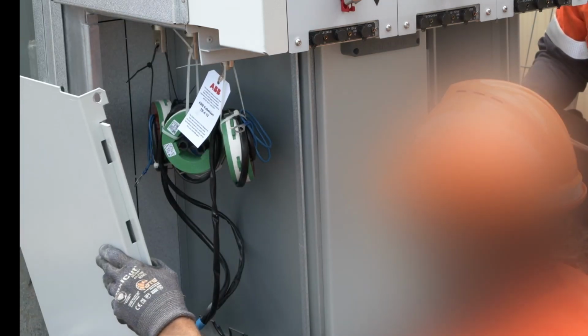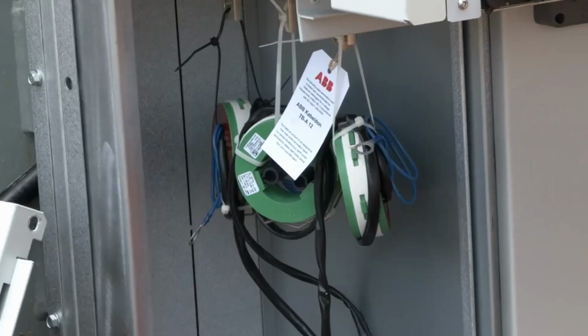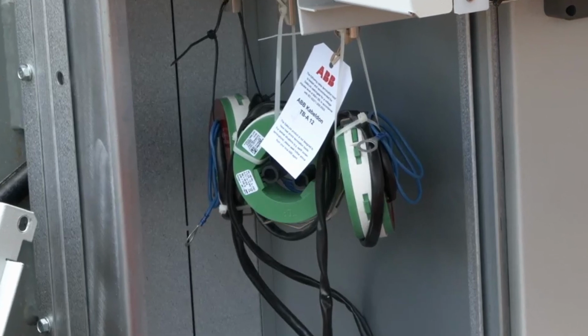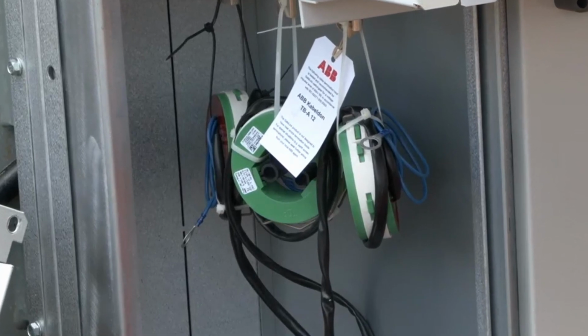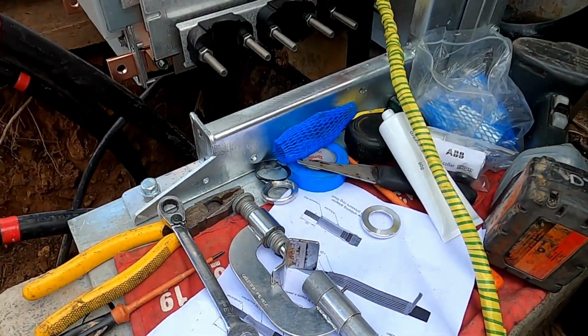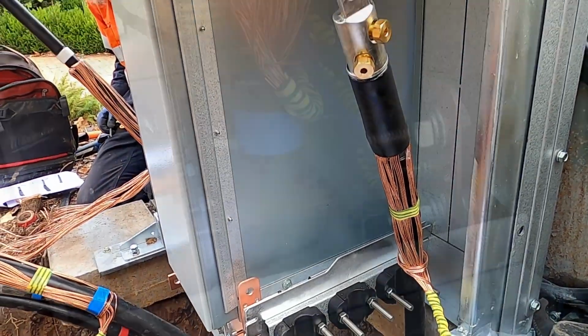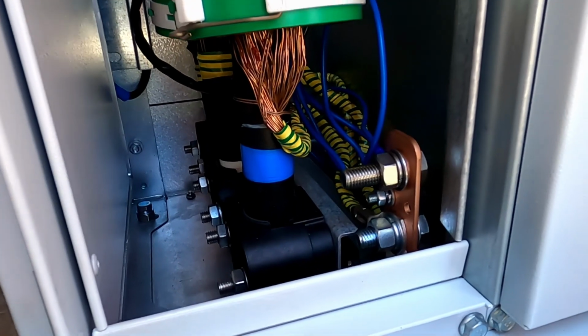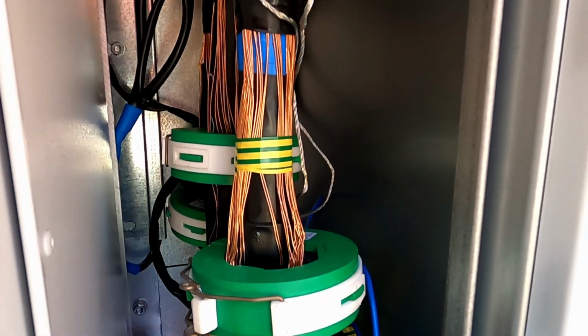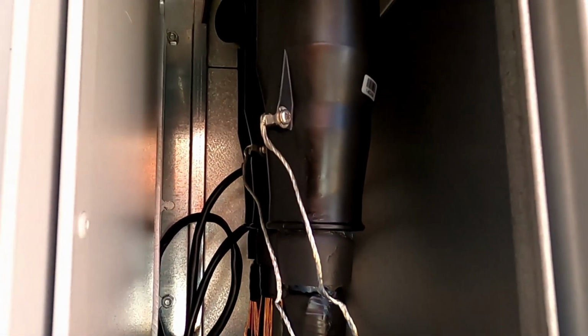Doors and side panels of the cable end boxes are removed to allow access for cable jointing. The CTs can be placed to the side until needed in the final stages of cable terminations. Perform all required cable jointing. Secure the cables into the brackets. Complete terminations as per kit instructions.